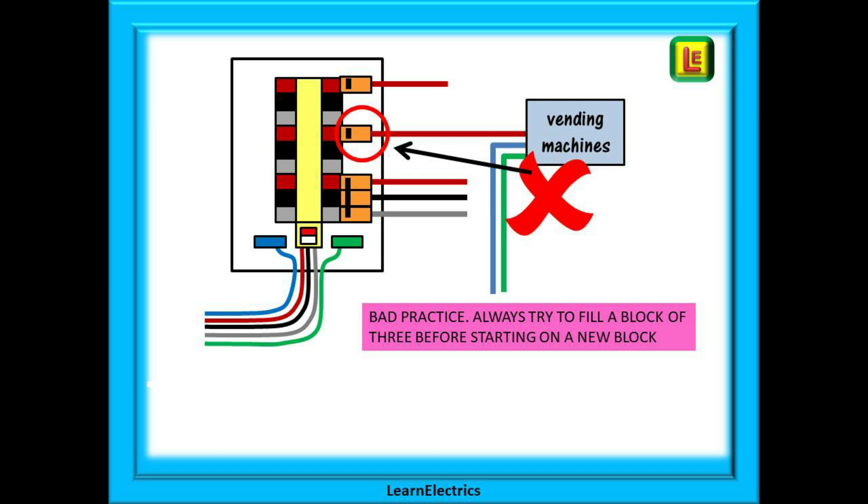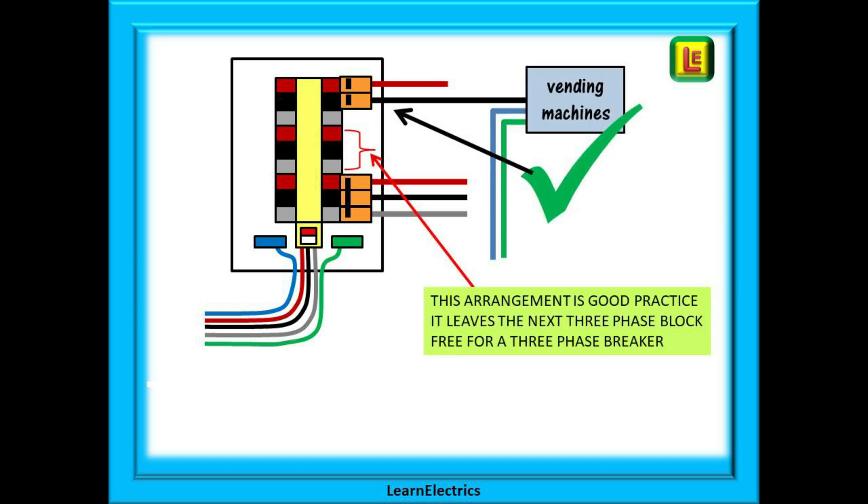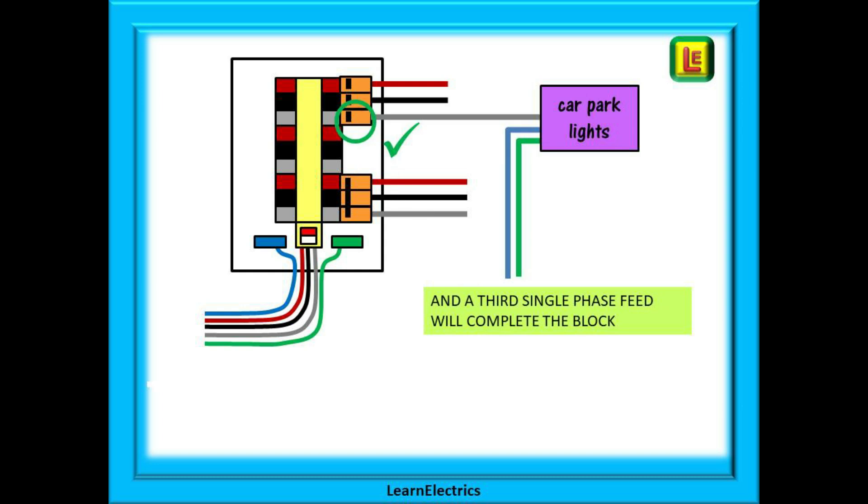And a three-phase breaker should span the brown, black, grey in that order. Again, it is bad practice to have a three-phase breaker across, say, grey, brown, black. So, let's rearrange things. This is the vending machine correctly connected into the board and it leaves the next single-phase way, the grey, free for another single-phase circuit and the three-phase blocks are free also. And now we can add a single-phase circuit for the car park lights. This fits nicely into the empty grey space.